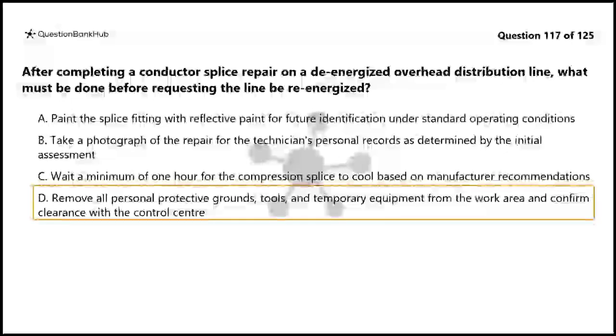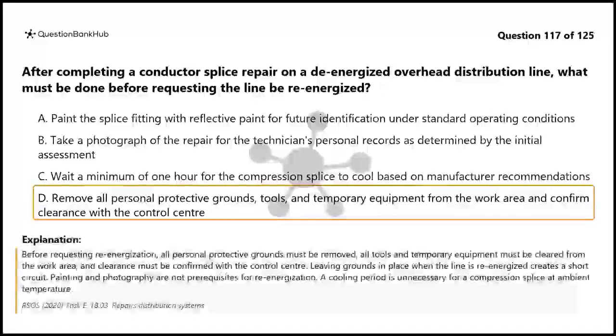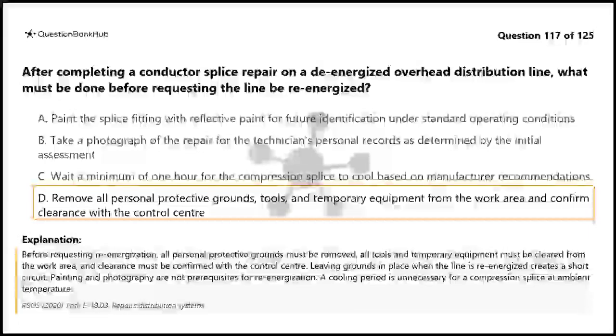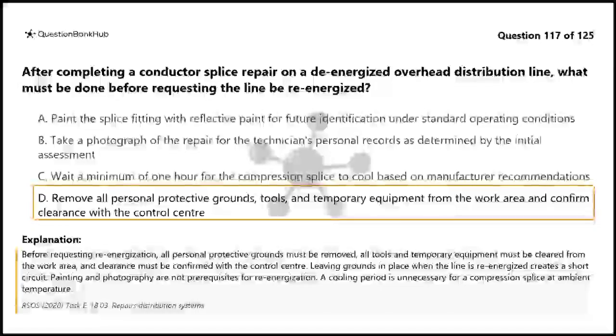The correct answer is D. Before requesting re-energization, all personal protective grounds must be removed, all tools and temporary equipment must be cleared from the work area, and clearance must be confirmed with the control center. Leaving grounds in place when the line is re-energized creates a short circuit. Painting and photography are not prerequisites for re-energization. A cooling period is unnecessary for a compression splice at ambient temperature.